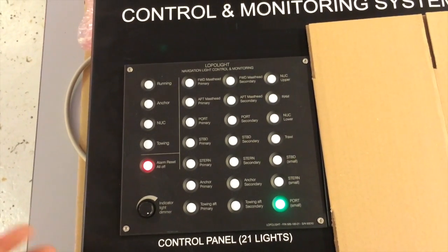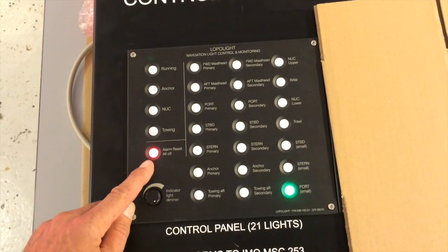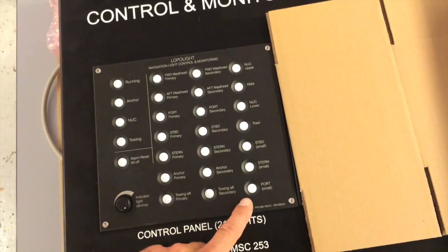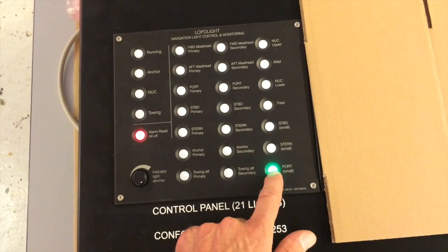If we have this, now I attempt to switch this on, but we still have the break, and you will see that within 10 seconds a new alarm condition will arise, although we have one power failure already. You'll see here in a second. So now you can see it starts blinking again. We can see that this is the troublesome one. I can mute it again. I can kill this lamp.